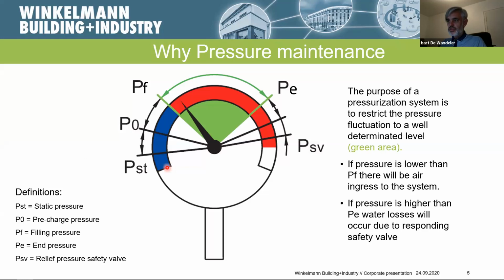Today, if we look at a pressure system, we have some definitions that you can also find on your own manometer in a system. It is quite easy. This is not high technology, not very difficult. It is easy to understand. We always start at the manometer, for example, with the static pressure. The static pressure is normally the height of your building. Let's say that in this example we work with 20 meters. That means that we need 2 bar in the system.